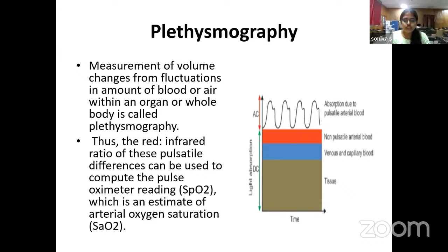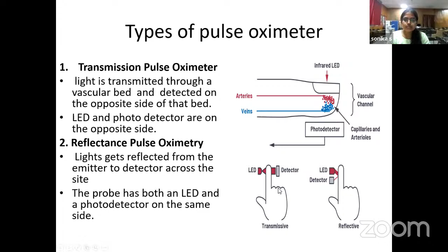Now coming to the types of pulse oximeter, we have two types. One is the transmission pulse oximeter, the other one is the reflectance pulse oximeter. In the transmission pulse oximeter, light is transmitted through the vascular bed and detected on the opposite side of the bed, wherein the LED and photodetector are kept on opposite sides. As in this diagram, we can see the LED and detector are kept on opposite sides of the bed. Whereas in the reflectance pulse oximeter, light gets reflected from the emitter to a detector across the side. The probe has both LED and detector on the same side.